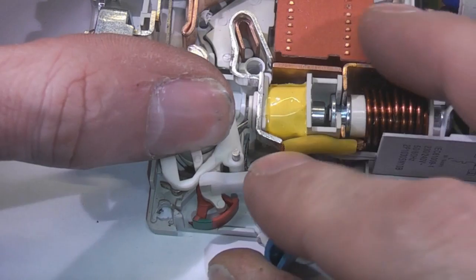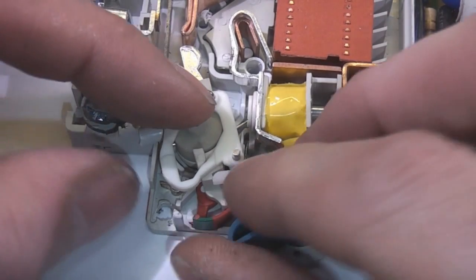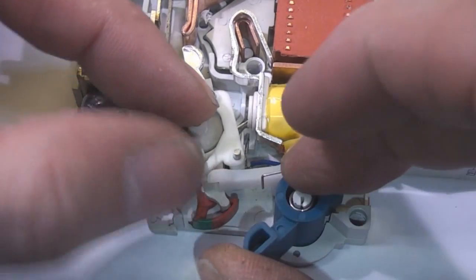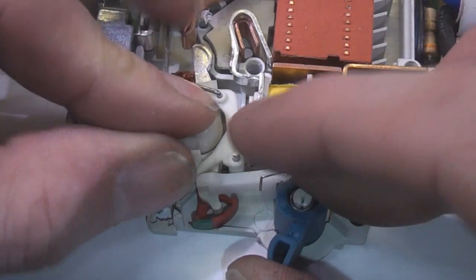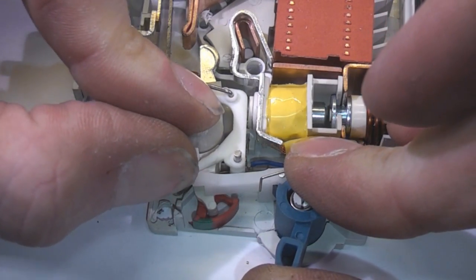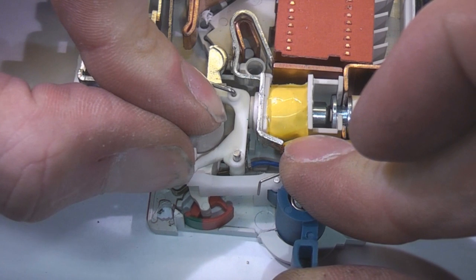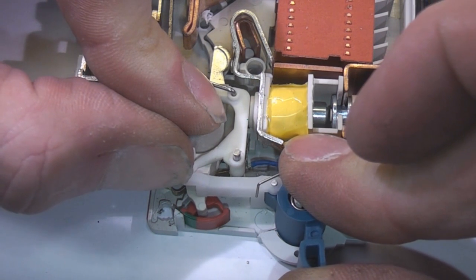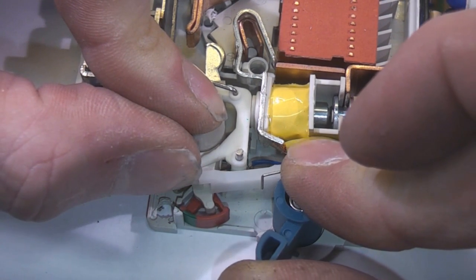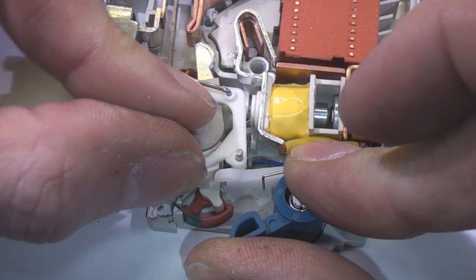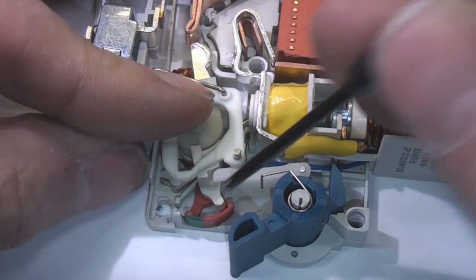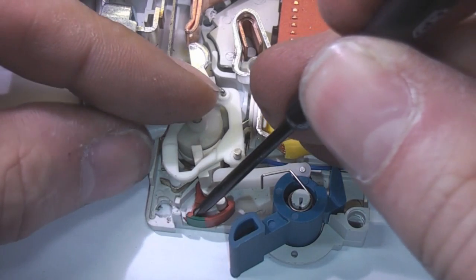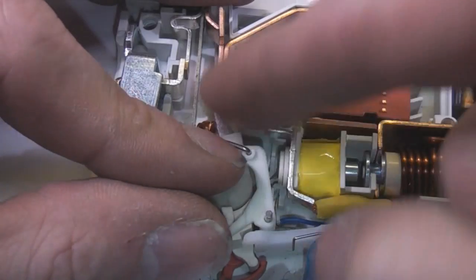So basically it fully turns on before it's a bit hard, because this hasn't got its top on, it's a bit hard to do this, but say as it turns on, it's only when it gets all the way on that it starts moving that flag, and then similarly when it turns off, it only turns off once it's gone all the way back to the fully open position. So this doesn't go green until this contact has gone all the way back to its fully open position, which is obviously a safety feature.